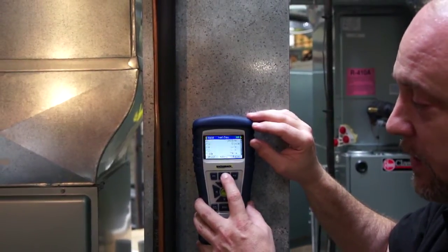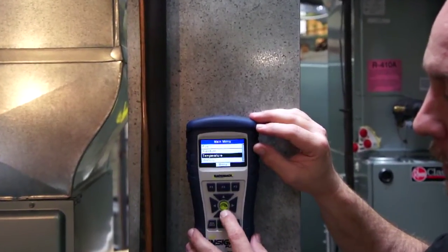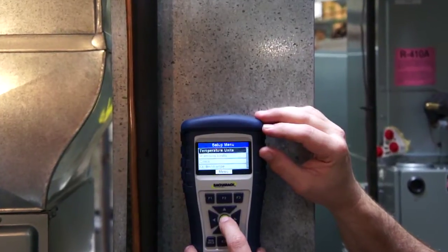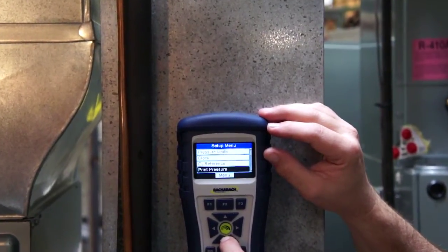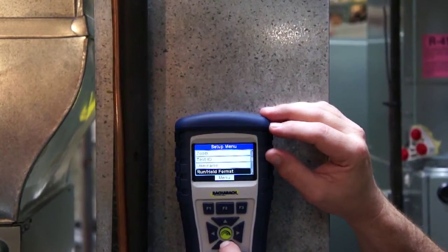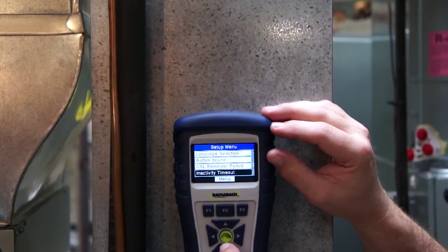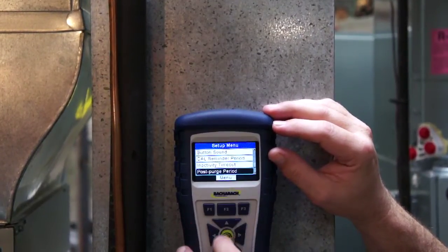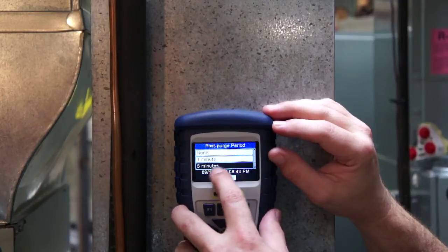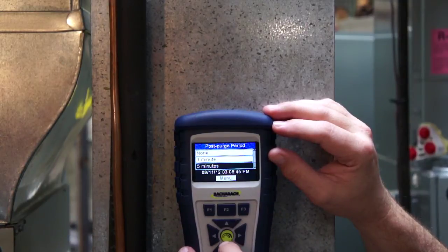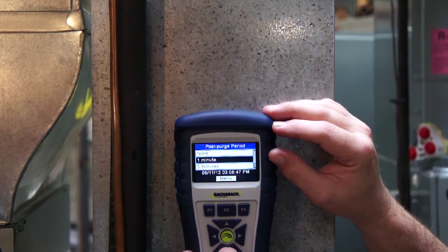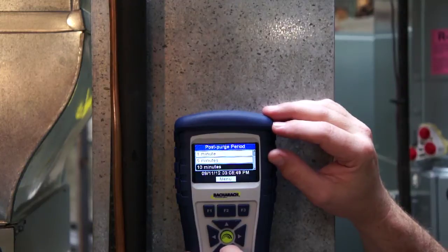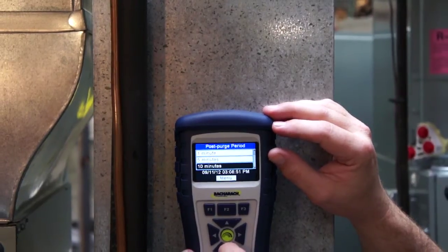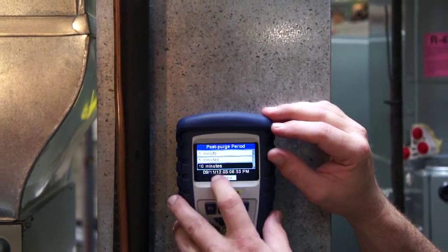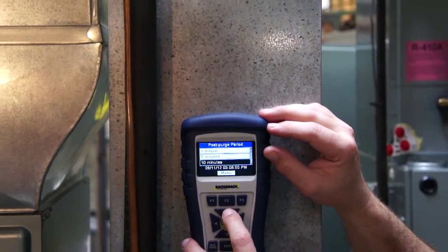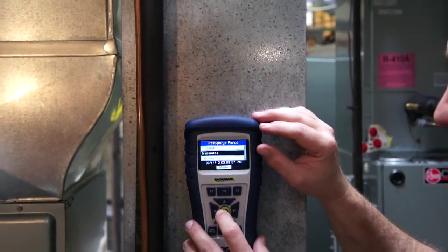So if you just hit the menu key and you scroll down here to get to the setup, you press enter, scroll down to come to the purge, which I might have passed it. There we go, post-purge period, hit enter. You want to set that to 5 minutes, which is what I have it set for. If you wanted to change that, you can go up or down. 5 minutes is the minimum time I'd recommend. If you are a little less conservative than I am, you might set that to 10 minutes to make that a little bit longer. But I'm going to set that to 5 minutes.